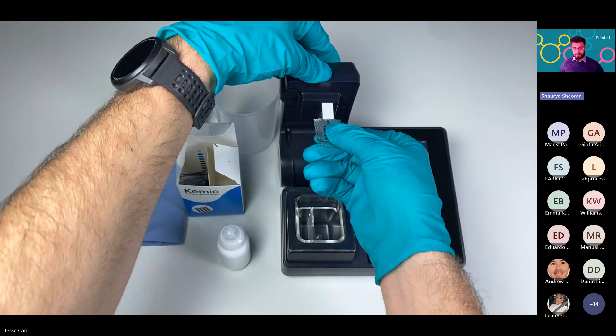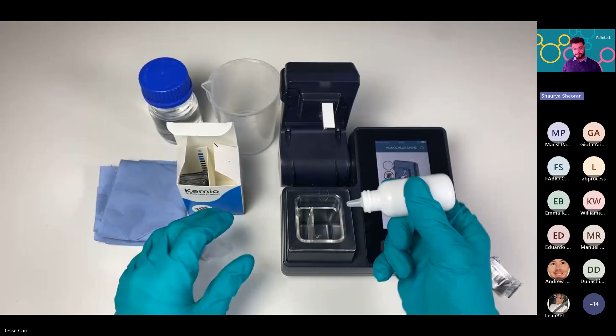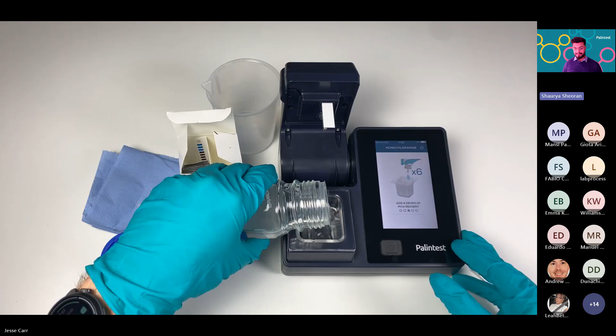Just going to open up the device and load in your sensor. You're going to tear the foil off. Make sure not to touch the surface of the sensor. Make sure to insert it with this red side facing down into the slot in the machine. Make sure it's fully seated. And then you're going to add your monochloramine reagent. This is just a compound to help with the conductivity and some of the pH buffering. Add 6 drops. And then we're going to add the sample that we want to test. See if I can't spill this. There we go. Just going to fill it up to the top of that vessel. And in terms of test prep, that's all there is to it. At this point, we can just close the arm and let the Kemio do its thing.